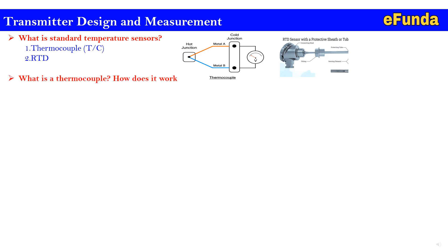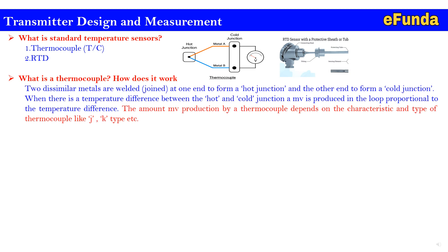What is a thermocouple and how does it work? Two dissimilar metals are welded — joined at one end to form a hot junction, and the other end forms a cold junction. When there is a temperature difference between the hot junction and the cold junction, a millivolt signal is produced in the loop which is proportional to that temperature difference. The amount of millivolt produced by a thermocouple depends on the characteristics and type of thermocouple, like J or K type, varying according to the material used for forming the junctions.